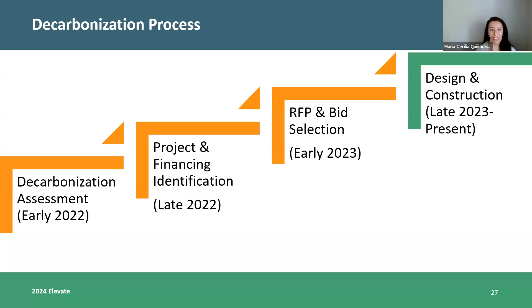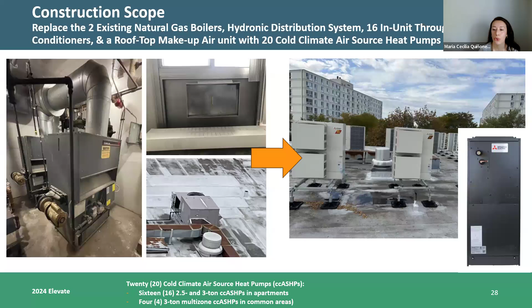This is what it's looking like, this is a heat pump. What you see on the left is the existing system: both big boilers, the through-wall AC unit in a typical apartment in the middle top, and the rooftop system at the bottom. All of that is being replaced with 16 cold climate air source heat pumps, either 2.5 or 3 ton, for the apartments, plus 4 three-ton multi-zone cold climate air source heat pumps to condition the common areas.